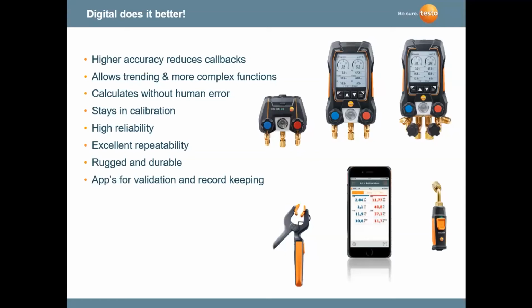If you have a technician that has two weeks experience in the field, all he needs to do is hook up the blue hose to the blue side, the red hose to the red side, put on the pipe clamp probes, one on the suction, one on the liquid, and the instrument is going to automatically calculate everything for him. He's going to get the same readings as he would as an experienced contractor that has 20, 25 years experience, because it's the instrument doing the work for you. All the service technician has to do is make sure that the probes are hooked up correctly at the right locations.